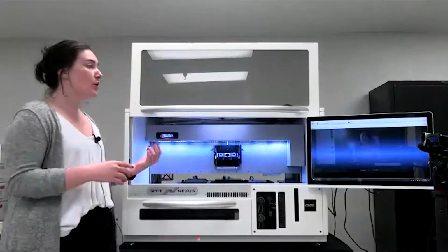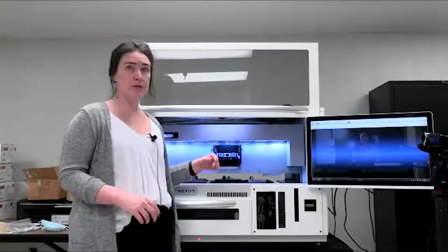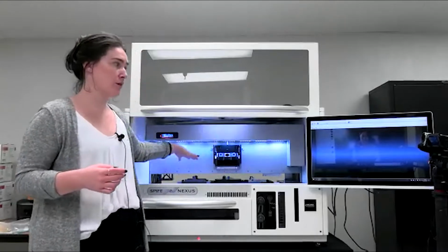All right. So we can talk a little bit about maintenance now. So as I mentioned, it should be primed every morning. Then we also talked about the spreader tip, which should be changed once a month. Also, your electrodes need to be cleaned on your electrophoresis platen cover. And we have a very easy maintenance function for that in the software. It's under the maintenance section. You'll just click clean platen cover.